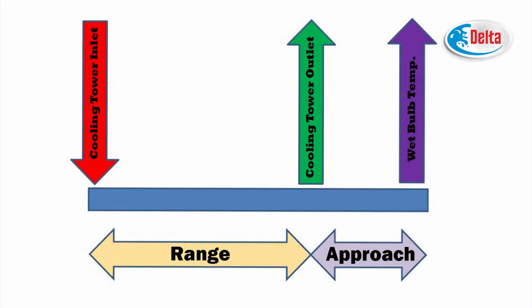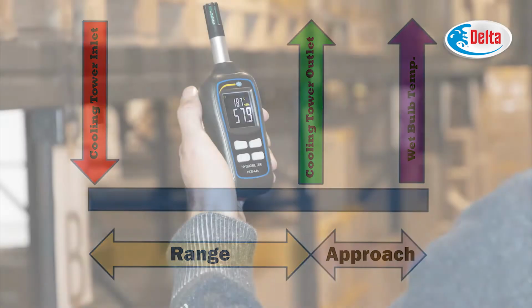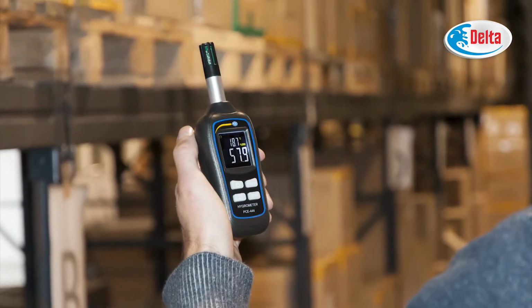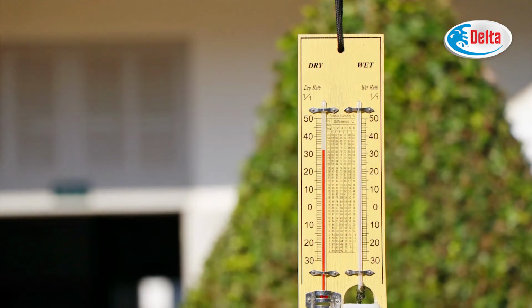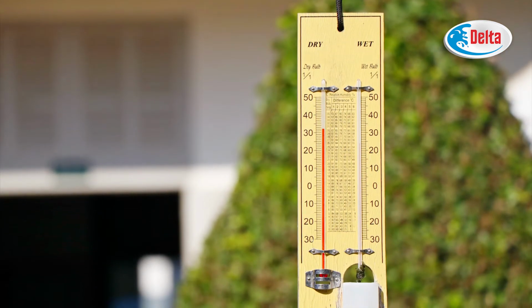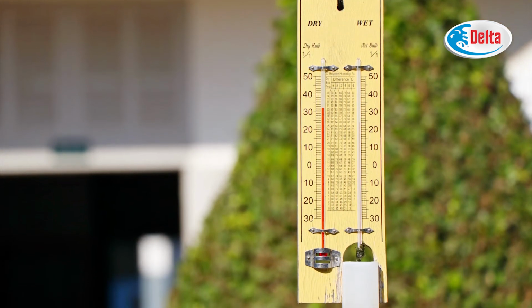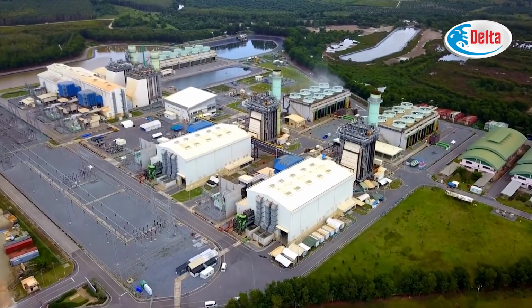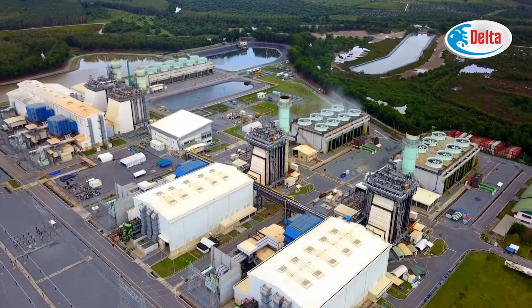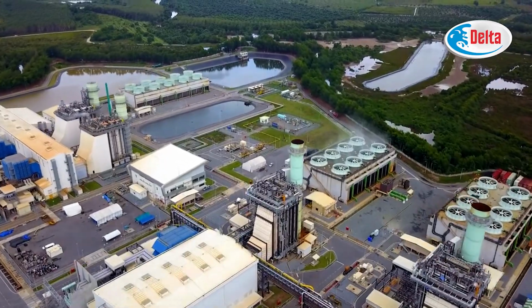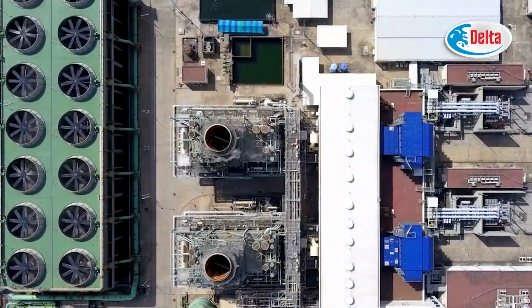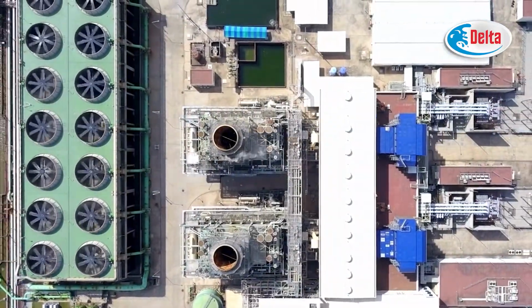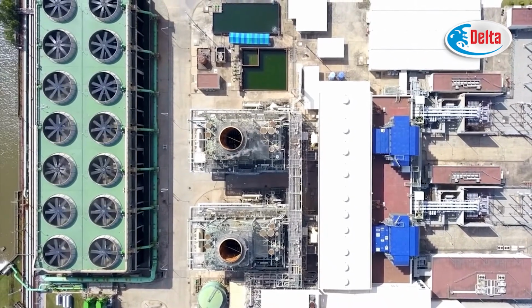The calculation of cooling tower efficiency involves the range and approach of the cooling tower and the ambient wet bulb temperature. In the ideal case, the cold water temperature will be equal to the wet bulb temperature. This is practically not possible to achieve. This requires a very large tower, and results in huge evaporation and windage, or drift loss, resulting in a practically not viable solution. In practice, the cooling tower efficiency will be between 70 to 75%.